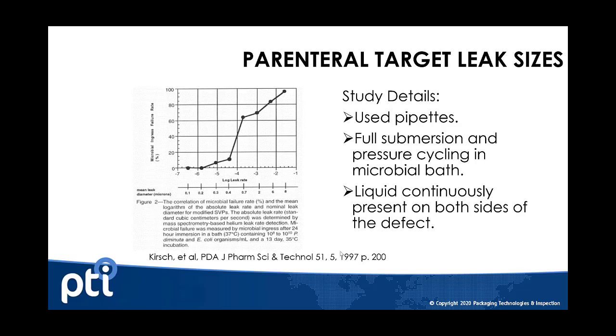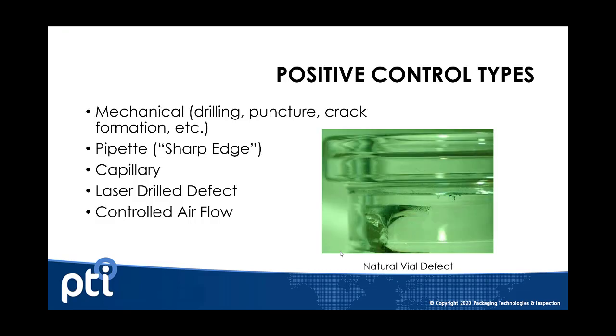There are a variety of ways that we can create that defect. Certainly the most natural type of positive control is the best way to go about proving a test method. You can make real defects by cracking the glass of a container, or tearing, making a puncture, or a crack in the body of a pouch or film material — that would be a mechanical type defect.